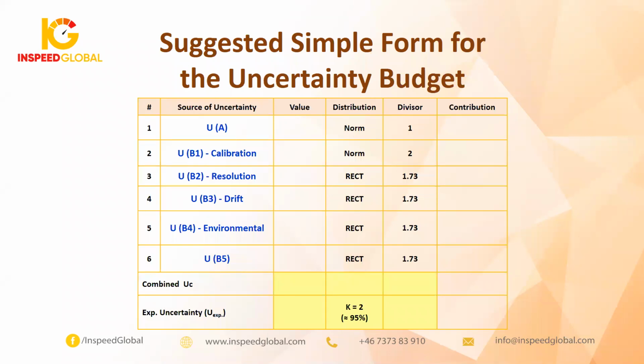Finally, for environmental, in a large number of laboratories it didn't have a direct effect on our measurement. But here you can see again, to review for type A, it is not constant, my dear. It is depending on your individual results. If you have 5 readings, 10 readings, 20 readings, 3 readings, whatever, for each test you are requested to get the value and get the mean, standard deviation, type A, or repeatability, and mention the results here in value. And divide this value by 1 to get the contribution here in the last column.